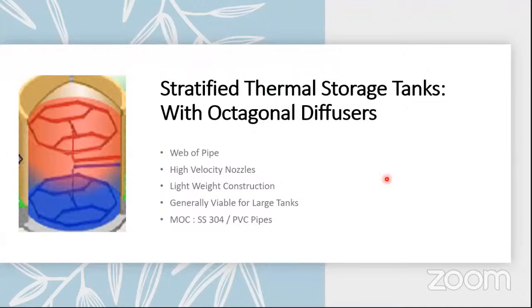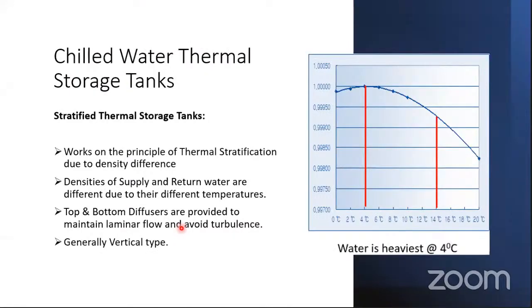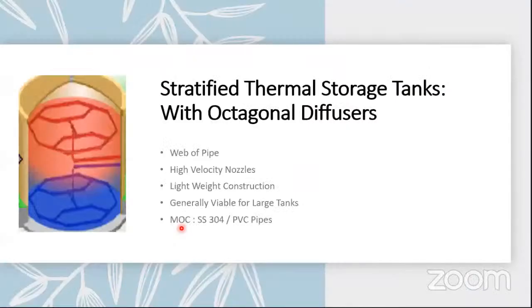Now, stratified tanks are also available with octagonal diffusers. In octagonal diffusers, there is a web of pipe, as you can see here in the picture. It has high velocity nozzles, it's lightweight in construction, and it is generally viable for very huge non-pressurized tanks. That also we will understand, what they are. And their MOC, the material of construction, is SS304 and PVC pipes, is what these diffusers are made of. We will talk about diffusers separately.